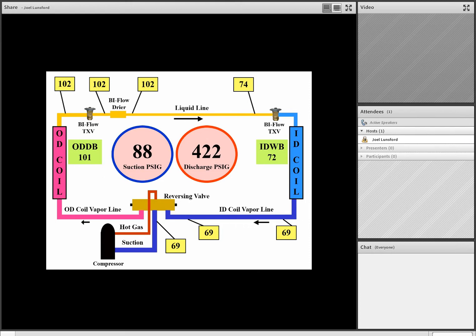But now hang on a second. Look at the difference between the outlet of the biflow dryer and the other end of the liquid line entering the biflow TXV inside. We have 102 degrees and 74 degrees. So we should never have any more than about 6 or 8 degrees temperature difference across that liquid line. However, in this example, we've got about 26 to 27 degrees temperature difference. So in this example, we see we have a restricted liquid line.